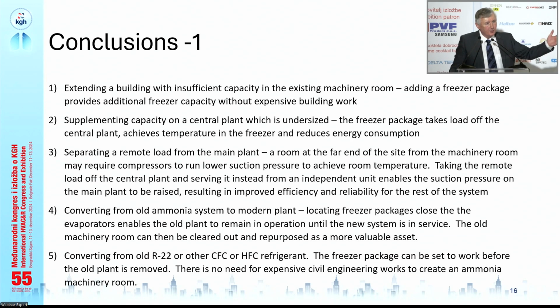The old machinery room, as you saw in the first case study, can then be cleared out and used for some other purpose. So actually they gained valuable real estate on the site as well. They now have a very nice maintenance workshop, which previously was an ammonia plant room. And then if you're converting from old R22 plant or some other CFC or HFC refrigerant, the freezer package can be set to work before the old plant is decommissioned, so there's no disruption to service at all. We've also done this with ice rinks, for example, replacing old R22 chillers with ammonia chillers and keeping the ice on the pad throughout the entire exercise with the switchover.